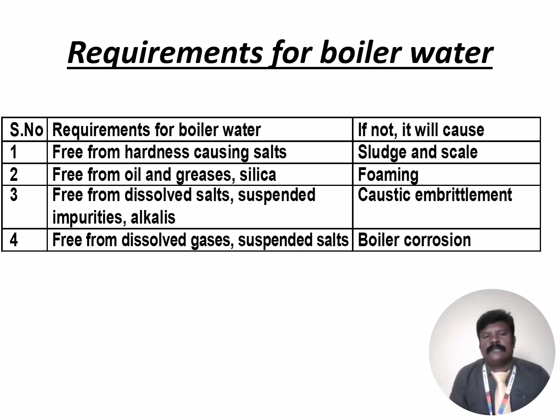sludge formation. Foaming. Foaming is a kind of stable bubbles on the boiler water sample, which do not break easily. They are very stable in nature. This is mainly due to the presence of oil, grease, and silica substances, suspended impurities of silica. Then caustic embrittlement. Caustic embrittlement is caused by the dissolved salts, suspended impurities, and alkali substances like sodium carbonate. And boiler corrosion is mainly caused by the dissolved gases like O2, CO2, and suspended salt.